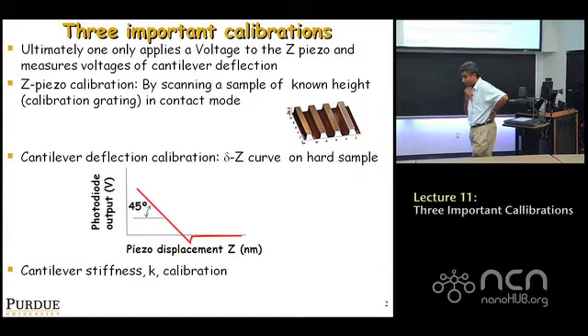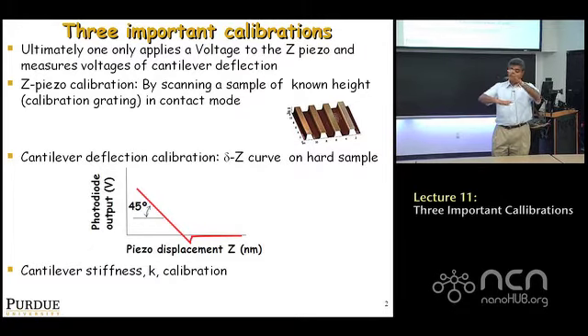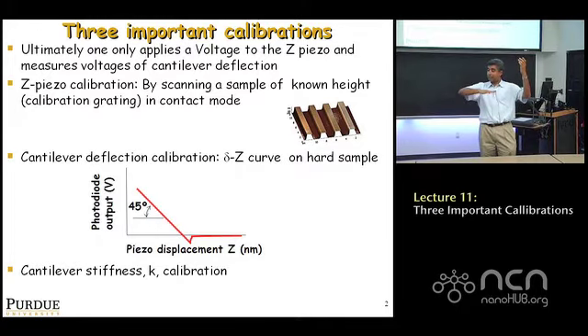The second calibration is cantilever deflection calibration, because remember, the whole premise of measuring interaction forces is as follows. When we have a photodiode, what you measure is the bending angle of the cantilever. This is a very important point, because if you look at the trigonometry, if a cantilever just moves up and down rigidly without bending, the laser spot position on the photodiode hardly moves at all. On the other hand, as it bends, there's a big amplification of this rotational bending signal. So the laser spot moves and displaces by a large amount on the photodiode, which is why what a photodiode measures is not absolute up and down position, but rather rotation angle or bending of the cantilever.